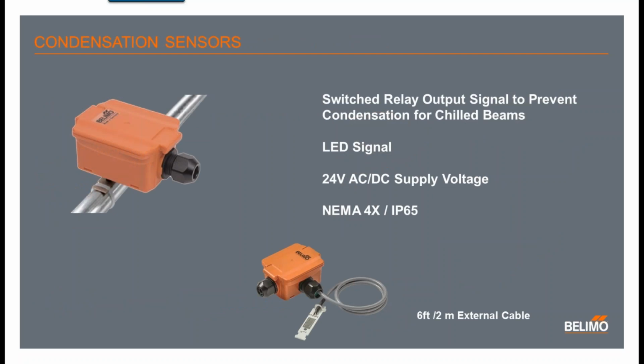Our condensation sensors provide a switched relay output signal to prevent condensation for chilled beam applications. They have an integrated LED signal for condensation alarming. They are 24 volt AC/DC supply, and again NEMA 4X. We also have an option with a 6' (2 meter) external cable for remote installations.